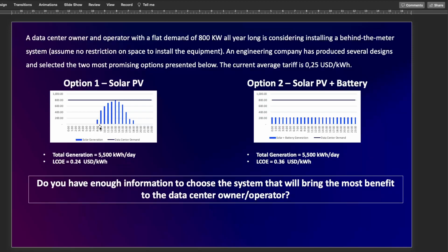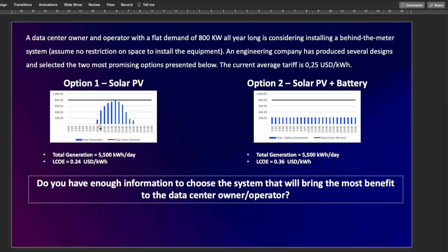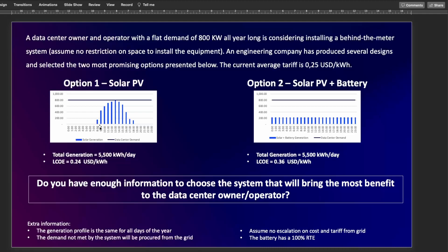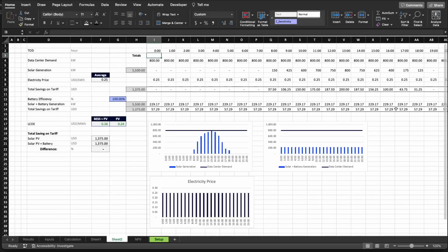Option two is a solar PV plus battery system that will produce a flat generation and a total generation per day of 5500 kilowatt hours, which is the same as option number one. But this system has an LCOE of 36 cents per kilowatt hour because of the cost of the battery. The question is, do you have enough information to choose the system that will bring the most benefit to the data center owner and operator? To complement it, we have some simplifications. We're going to assume the generation profile is the same for all days of the year, there is no variation in the production, the demand not met by the system will be procured from the grid, we're going to assume there is no escalation on costs and tariffs from the grid, and the battery has 100% round trip efficiency. Pause the video and answer below if you think we have or don't have enough information to choose between option one and option two.